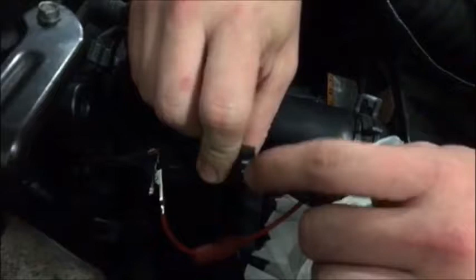Right here it has 2 of the same colors, which most of the time is the heater side, and the other side is for the signal. If you ever want to check to see if the sensor is good, you can check the 2 wires for ohms. If it says OL, there's an open in the wire. If it says 0.00 ohms, there's a short somewhere. But you should always be seeing some kind of resistance in the sensor to know it's working.